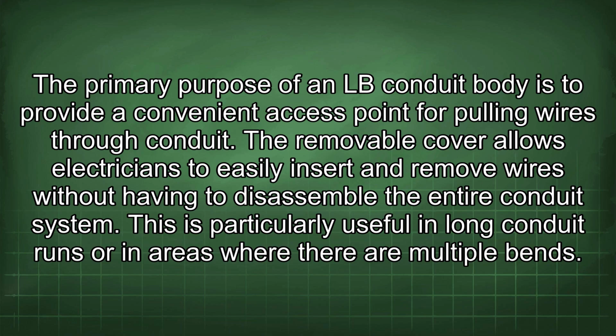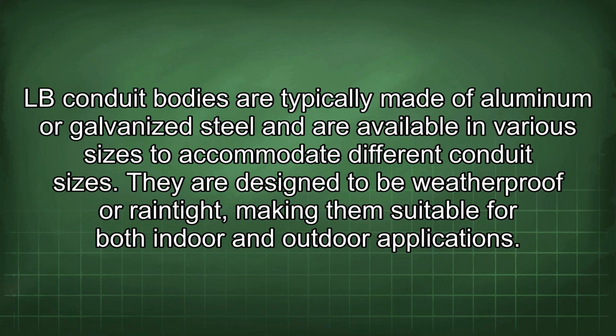The removable cover allows electricians to easily insert and remove wires without having to disassemble the entire conduit system. This is particularly useful in long conduit runs or in areas where there are multiple bends. LB conduit bodies are typically made of aluminum or galvanized steel and are available in various sizes to accommodate different conduit sizes. They are designed to be weatherproof or rain-tight, making them suitable for both indoor and outdoor applications.